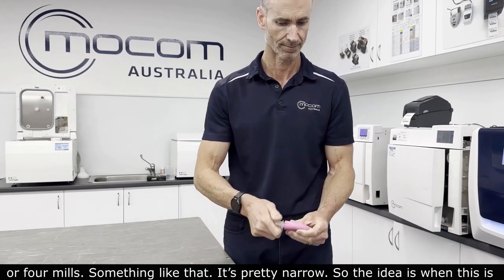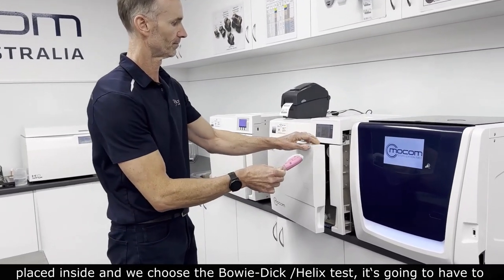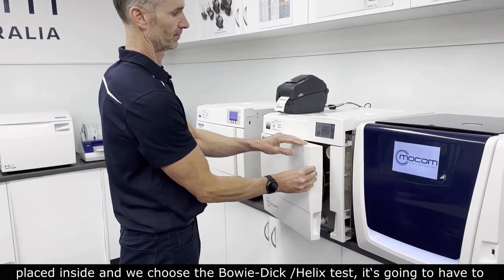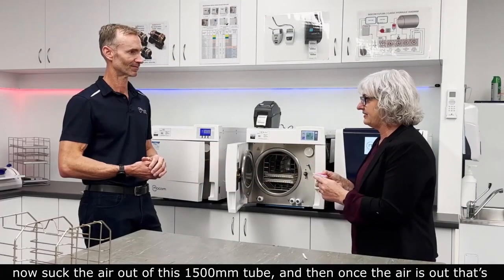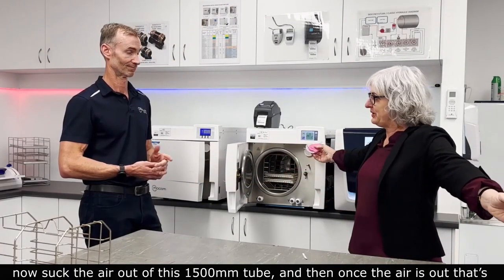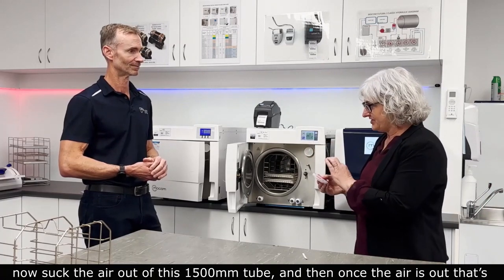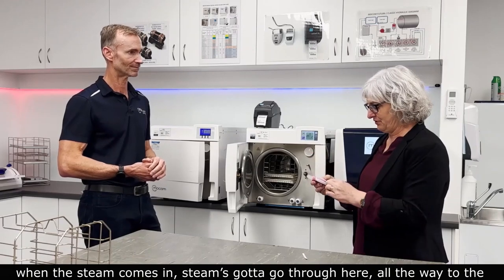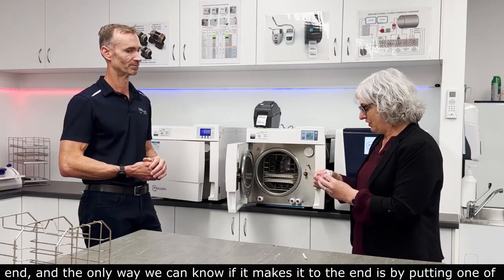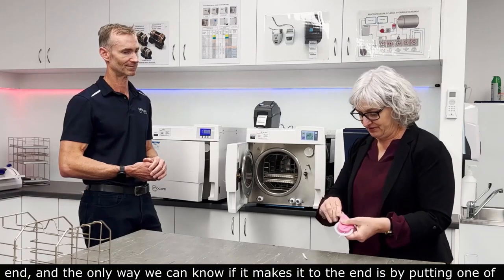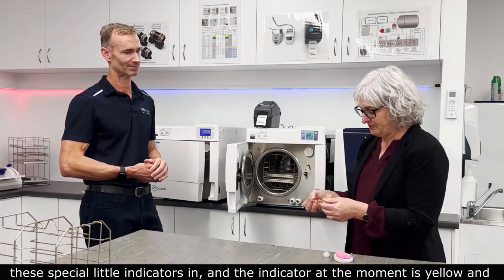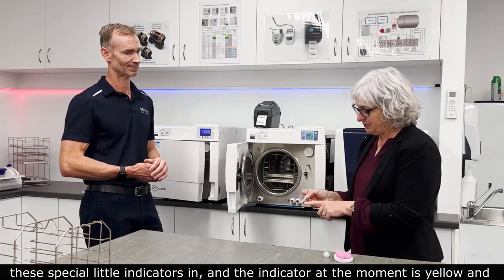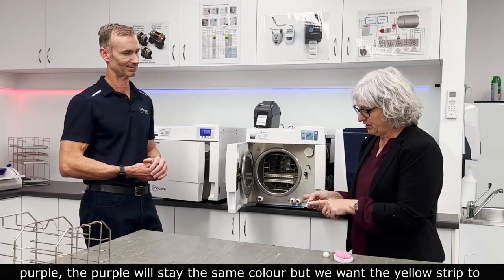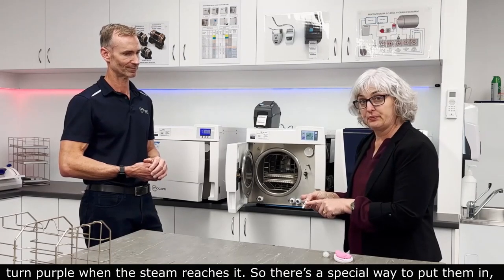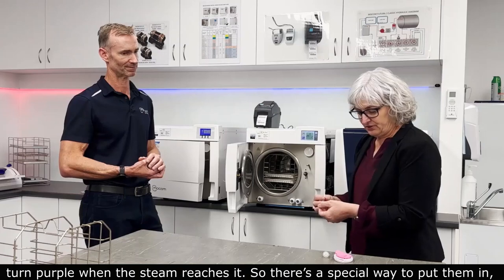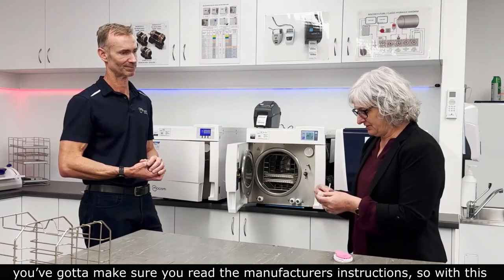Three mils? Something like that—pretty narrow. So the idea is when this is placed inside and we choose the Bowie-Dick/Helix test, it has to suck the air out of this 1500 millimeter tube. Then once the air's out, the steam comes in and has to go through here all the way to the end. The only way we can know it makes it to the end is by putting one of these special little indicators in. The indicator is currently yellow and purple—the purple stays the same colour, but we want the yellow strips to turn purple when the steam reaches it. There's a special way to put them in, so make sure you read the manufacturer's instructions.